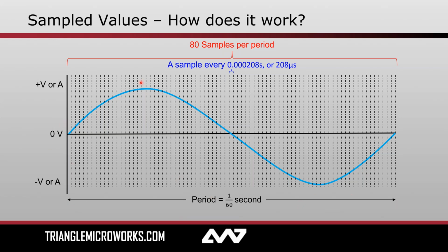In that time frame, my typical sine wave is going to pass up, come back down, and rise again. In that time, we're going to take 80 samples. In 1/60th of a second, we divide that up into 80 chunks and grab the value of the waveform at each point, resulting in a sample being taken every 208 microseconds.